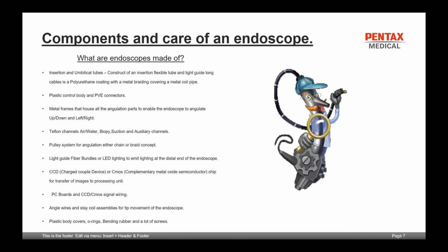Okay, so what are endoscopes made of? Endoscopes are an insertion tube and the umbilical tubes. The construct of the insertion of the flexible tubes and the light guide long cable is a polyurethane plastic coating with a metal braiding covering metal coil pipes. So that's basically going to house everything internally. So all your stuffing goes through the insertion tube.